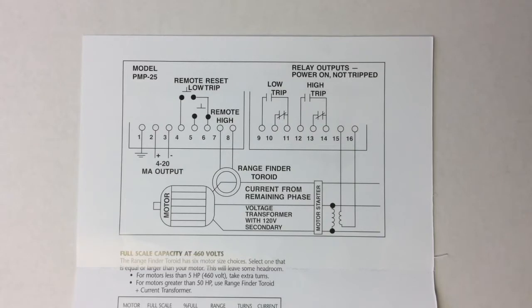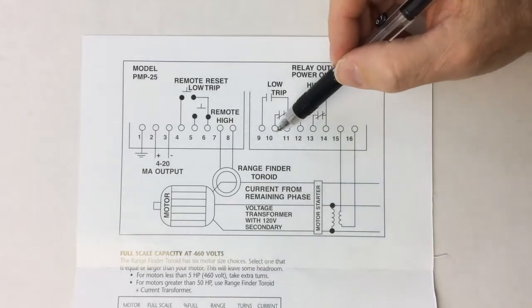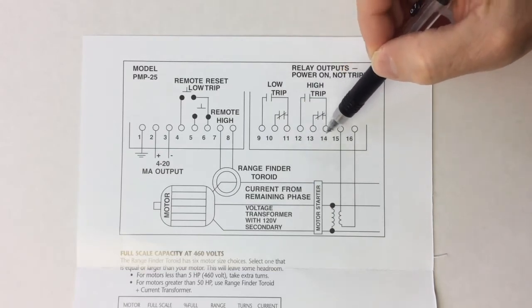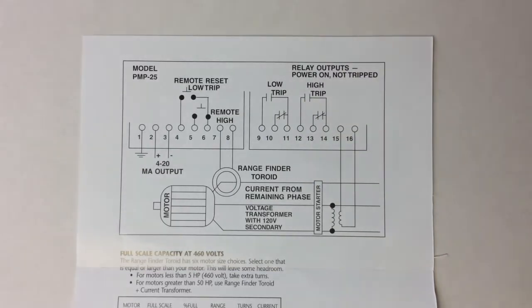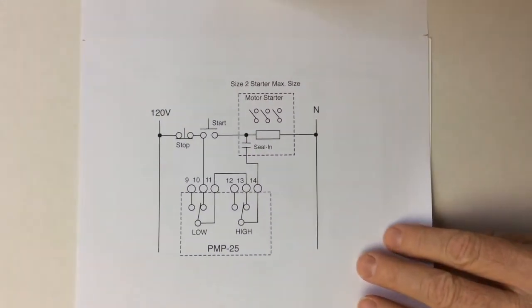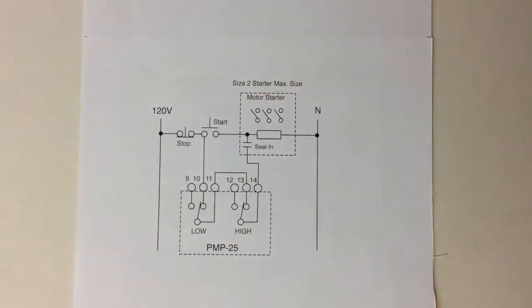In a typical application, the normally closed relay contacts for both high and low are wired in series with a motor starter stop circuit. This diagram shows the PMP25 high and low closed contacts wired in series with the seal-in contact of a motor starter.